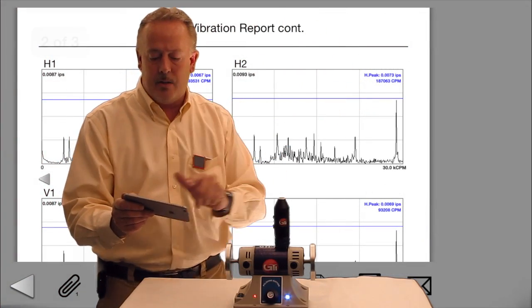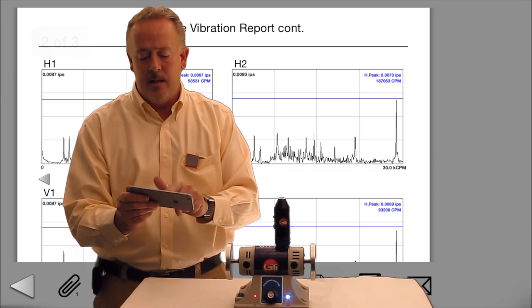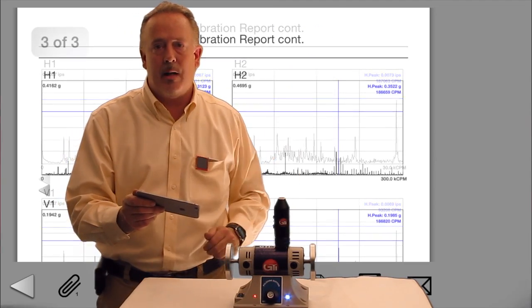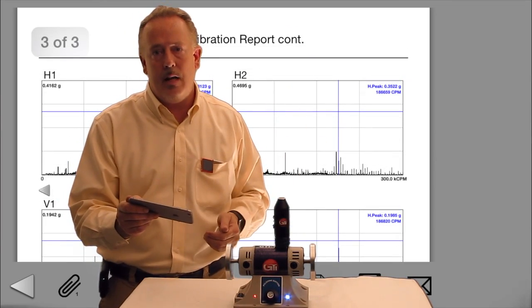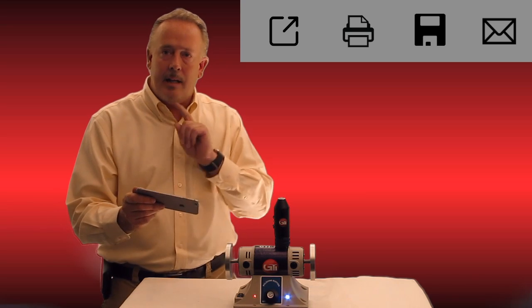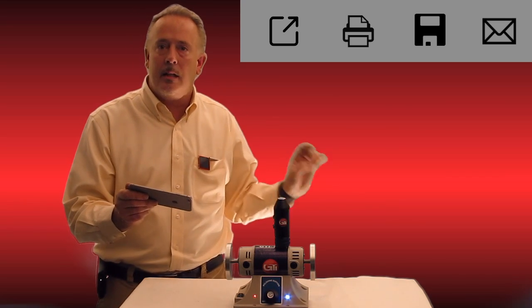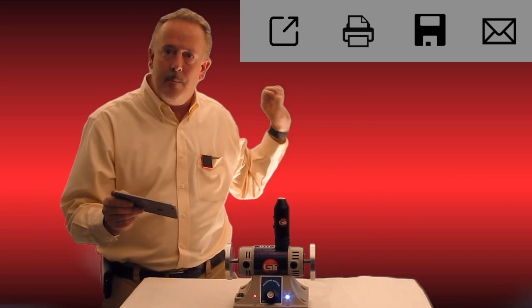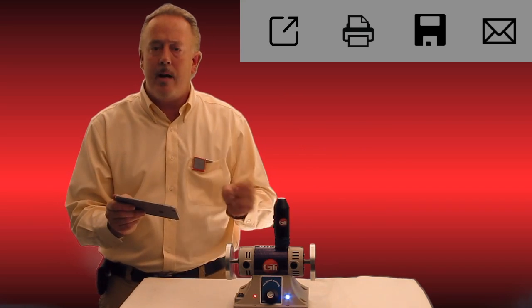And as you see me scroll down here, now we've got our velocity spectrums, every single one I've taken, and my acceleration spectrums, every single one I've taken. And that's all built into the report. And as you can see on the bottom of the screen, I can simply email that, I can save it to the app to email it later, or I can wirelessly print to a local wireless printer right on the network.